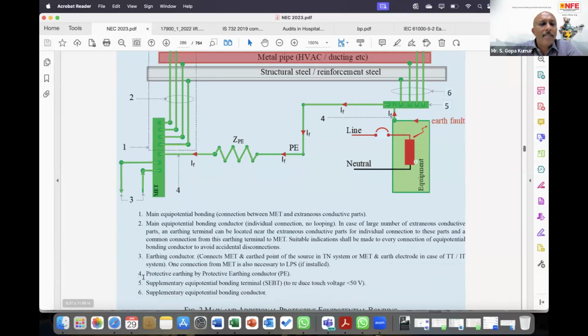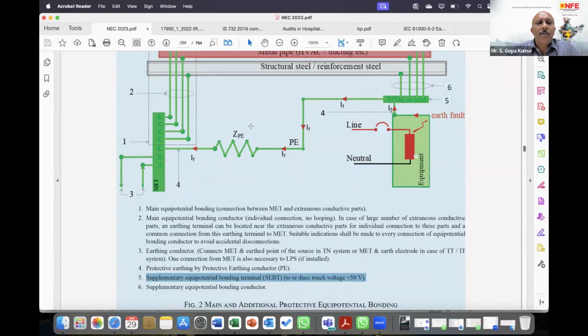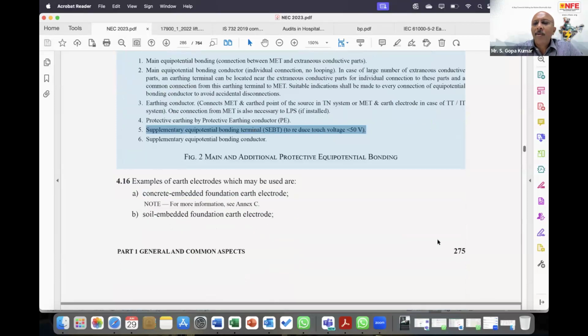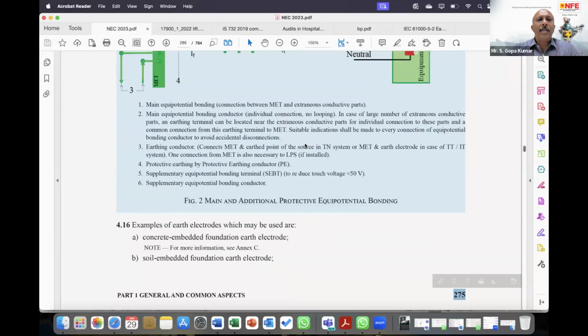Then the requirement is supplementary equipotential bonding to reduce the touch voltage to less than 50 volts. This is what is required. So basically, you need this connection at multiple places. I would recommend you go through this. It is on page number 275 of the NEC. Look at those page numbers and you will be able to get the answer.